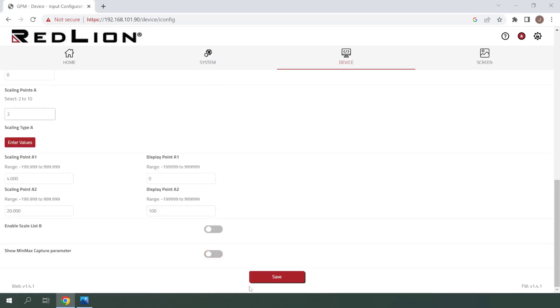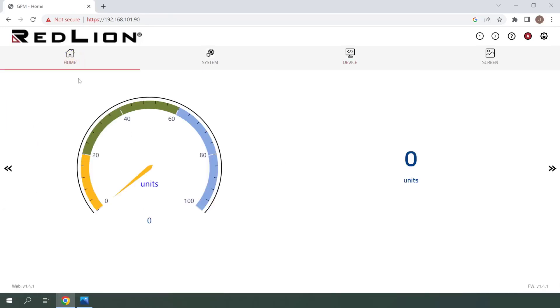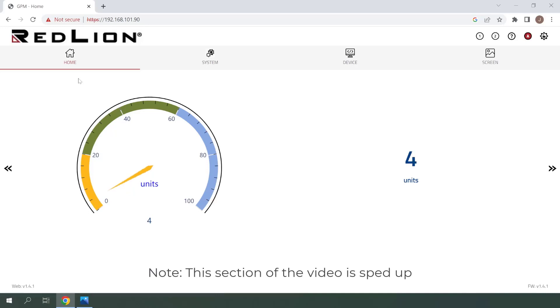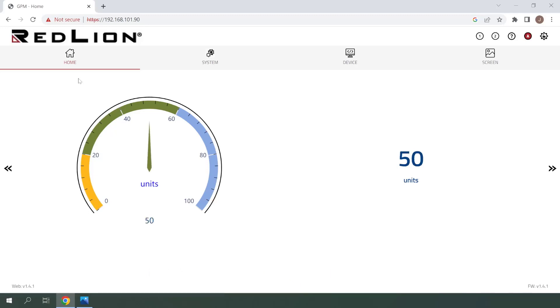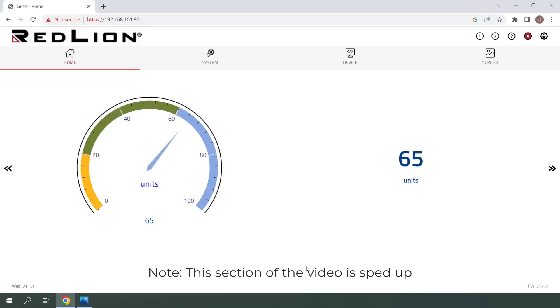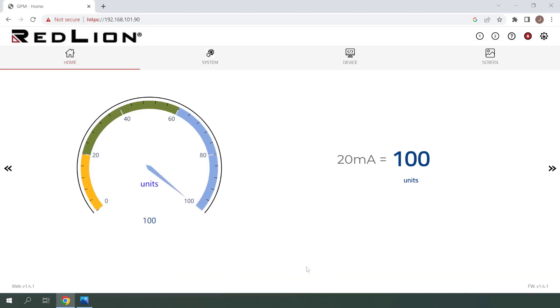At this point, we can test our newly configured 4 to 20 milliamp signal input. I'll click save and then navigate back home so that we can watch our signal in real time. My signal generator is currently set to 4 milliamps, which is displaying 0 as expected. Now I'll begin to increase the signal to 12 milliamps, and you'll see that we approach a value of 50, as this is 50% of our analog scale. As you can see, 12 milliamps gave us a value of 50, as expected. Now I'll start to increase the signal to 20 milliamps so that we can see it reach its full value of 100. And as you can see, 20 milliamps gave us a value of 100, as expected.